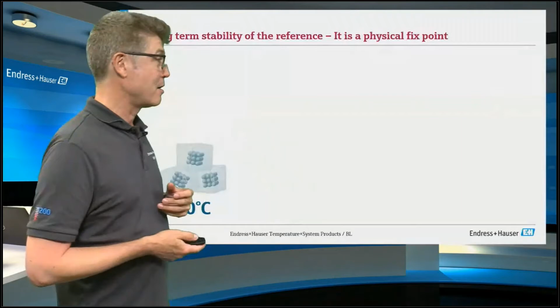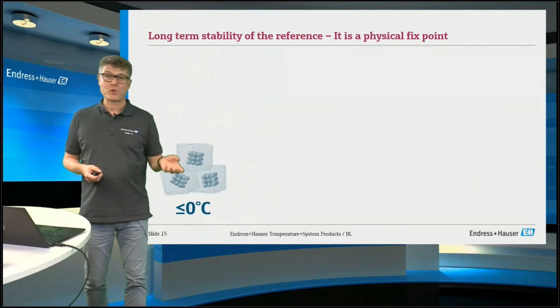This is really one of the standard questions. Yeah, your fixed point, how often you need to calibrate the fixed point and how you can calibrate the fixed point. And my answer to this is, yeah, in the same way like you do the calibration maybe now, maybe today. The standard way to perform a calibration for temperature sensors, and yeah, it's written in the standard, is to calibrate it in melting ice. So if you have ice cubes, they will melt at 0 degrees.